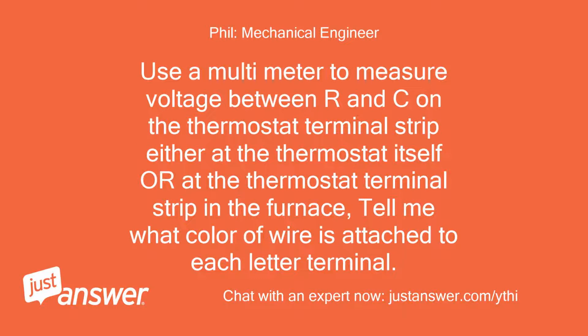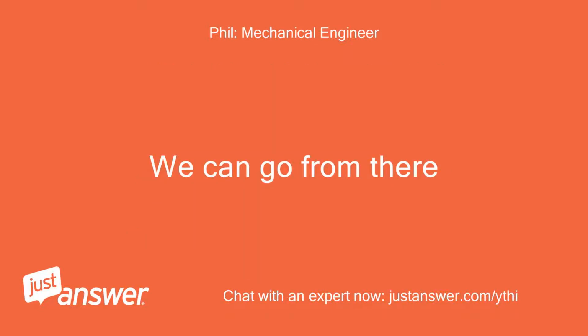Use a multimeter to measure voltage between R and C on the thermostat terminal strip, either at the thermostat itself or at the thermostat terminal strip in the furnace. Tell me what color of wire is attached to each letter terminal. We can go from there.